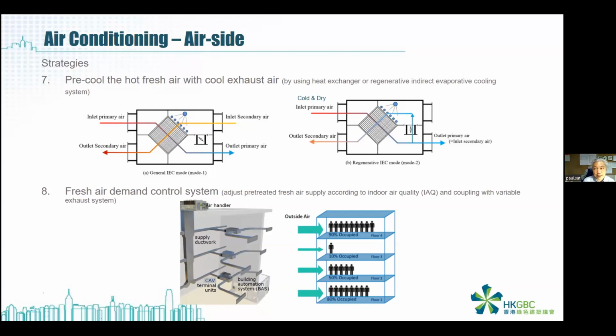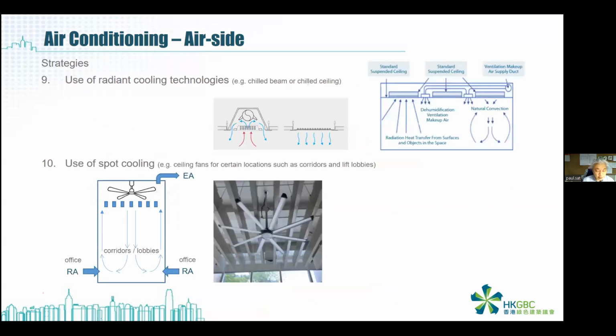We have a demo or a showcase in the latest. And another thing is that we can use fresh air demand control. This is very common because in hot summers, when you take in fresh air for occupants to breathe, you need to cool down the fresh air. In order to minimize this cooling energy, you need to do some demand control to limit the amount of fresh air intake in summer. But in winter, the air becomes cool, and this is a cooling source. You can use this cooling source to cool the systems.